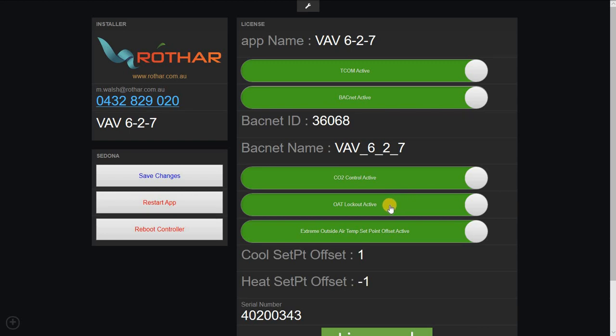If you want to use an outside air temp lockout, we've got it programmed because we live in the subtropics. If the outside air temperature is greater than 28 degrees Celsius, we won't allow any electric duct heaters to operate over 28 degrees. This is for energy savings, and if it's 28 degrees, it's hot, so you don't need the heaters anyway. This is a global outside air offset point if you want to enable that or disable it. So if it gets above 32 degrees Celsius, you can apply an offset to the set point. If it gets below 10 degrees Celsius, you can also provide an offset, and you can set those values here.